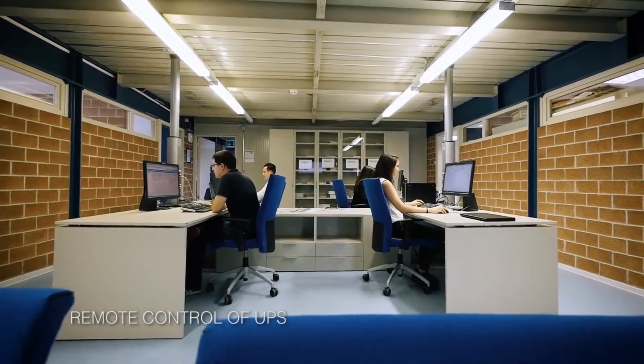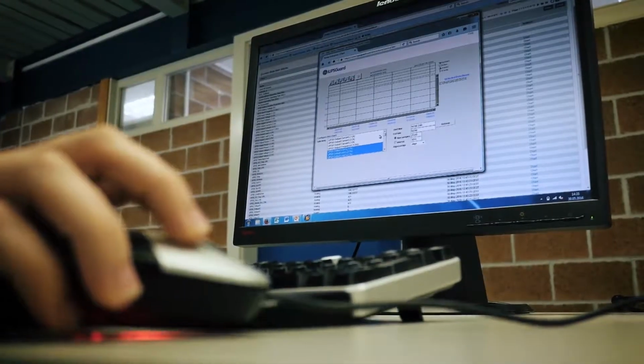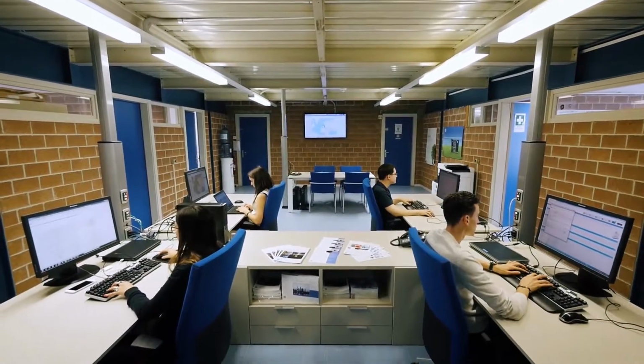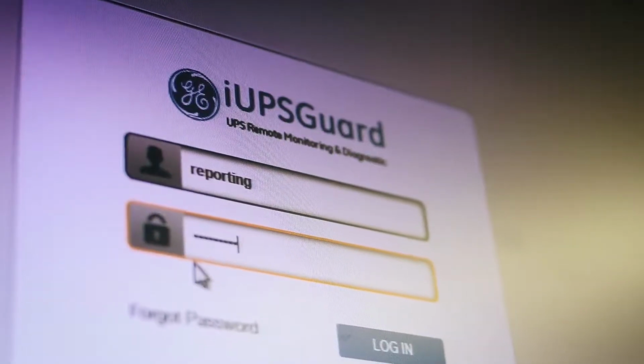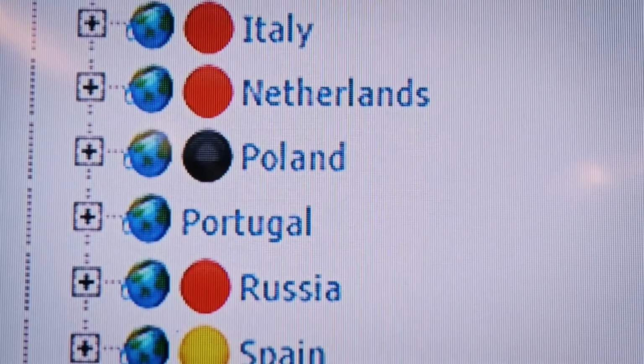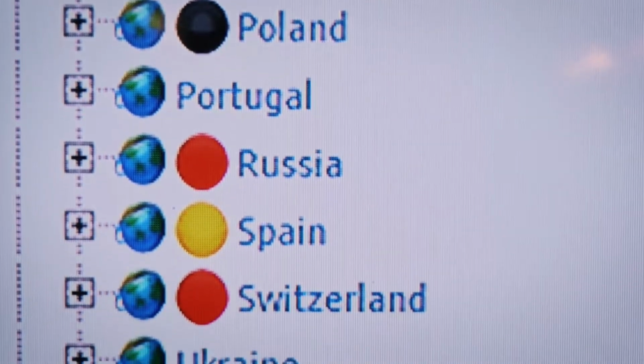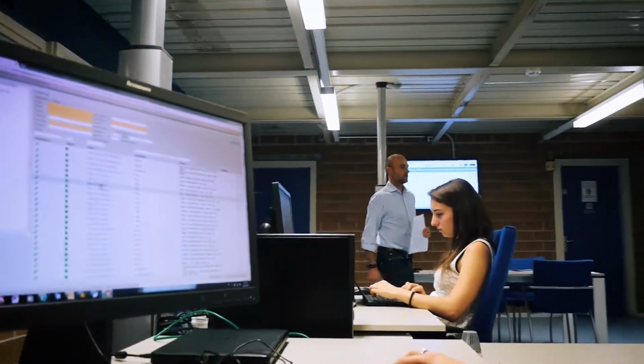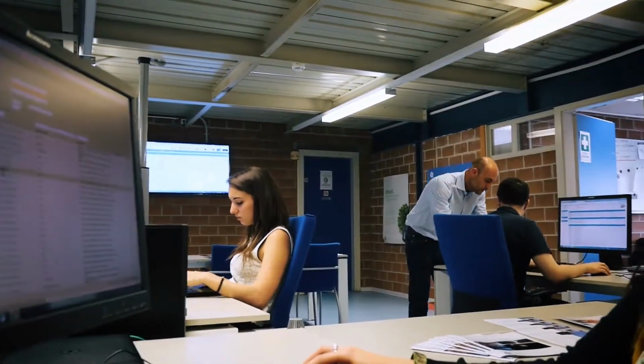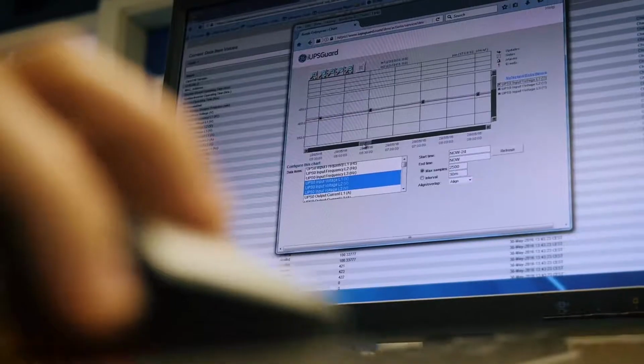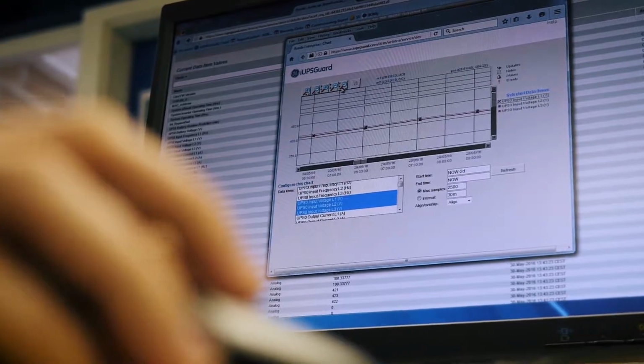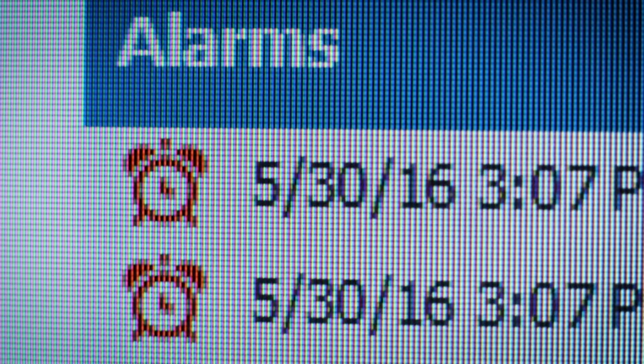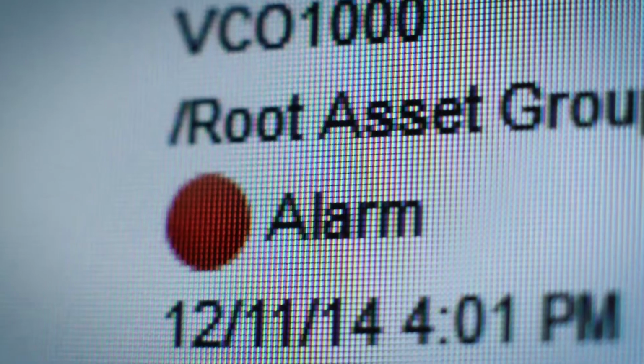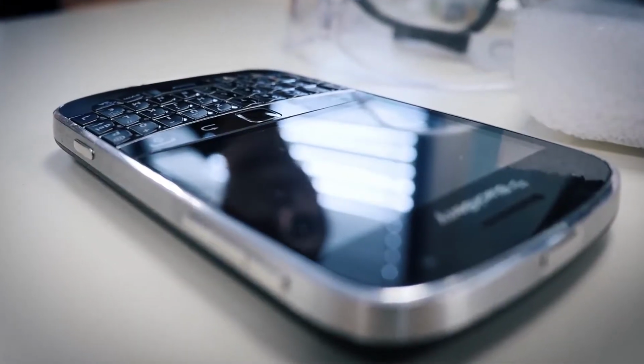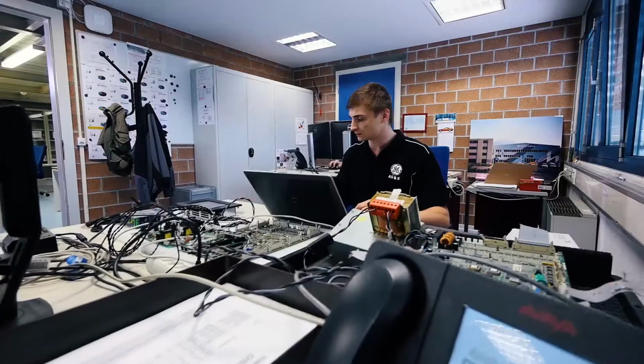UPSs are connected to a remote monitoring system that works constantly. This is the UPS Remote Monitoring Center, where GE utilizes the iUPS Guard monitoring system and UPS installed worldwide to ensure systems are operating properly. Reports are periodically delivered to customers to share system performance. When a UPS generates an alarm, it immediately reports to the monitoring center, where engineers investigate system conditions and, when necessary, take appropriate action.